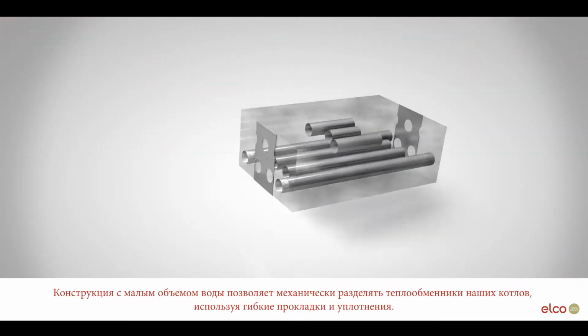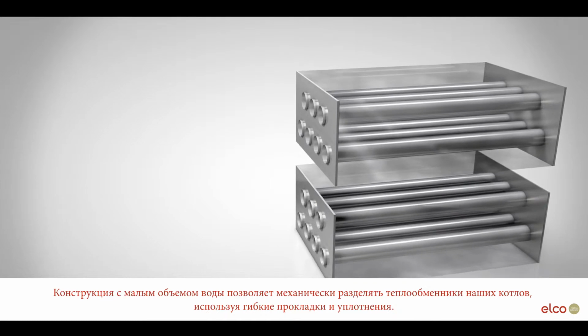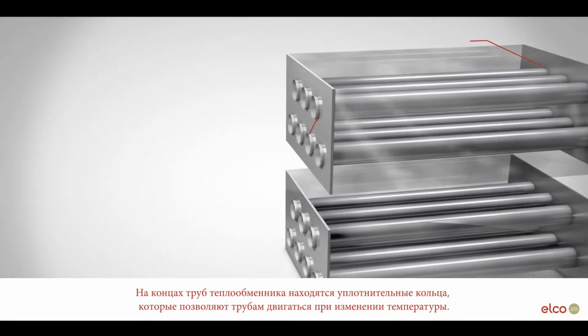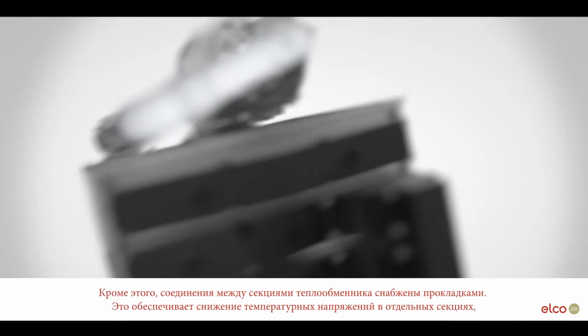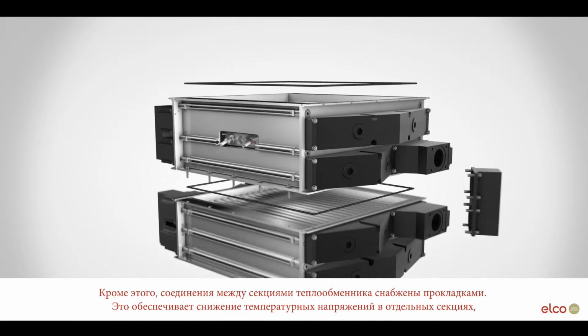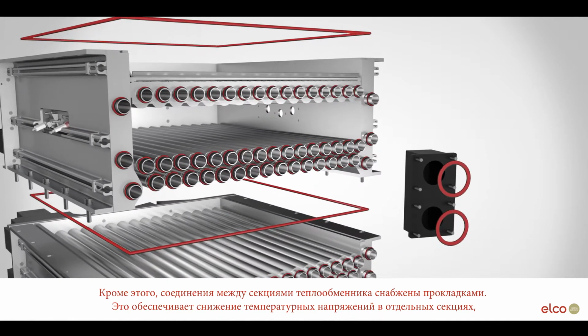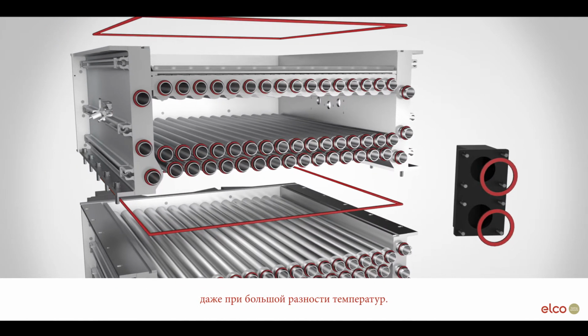On the contrary, our low water content boiler design allows our heat exchangers to be mechanically decoupled, using flexible seals and gaskets. The heat exchanger tubes are mounted in O-ring seals, allowing them to move or expand under influence of temperature changes. Additionally, several sections are mounted together with gasket connections. This ensures less temperature difference in one section, avoiding mechanical stress even at higher delta T operation.